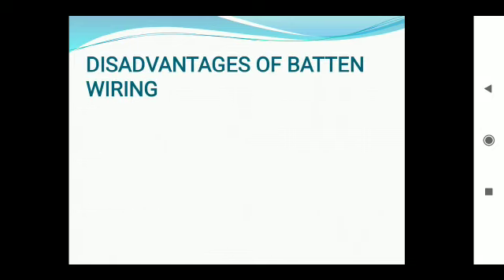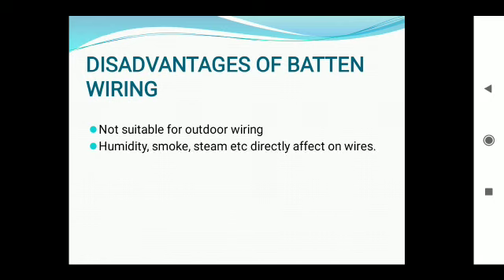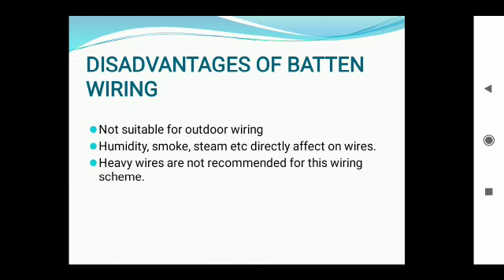Now the disadvantages of batten wiring: not suitable for outdoor wiring because this is an unenclosed wiring. Humidity, smoke, steam, etc. directly affect the wires. Heavy wires are not recommended for this wiring scheme because the link clips are unable to attach heavy wires. Only suitable for below 250 volts, or this is suitable for low voltage installation, and there is a high risk of fire.